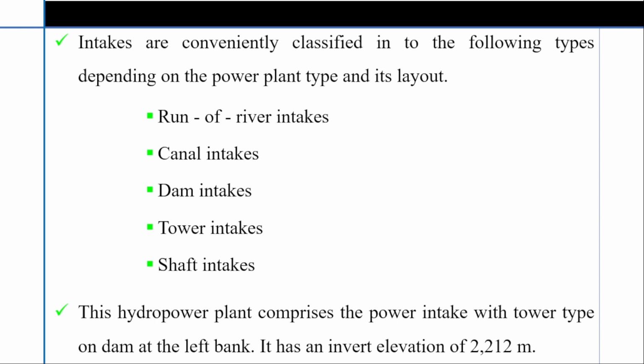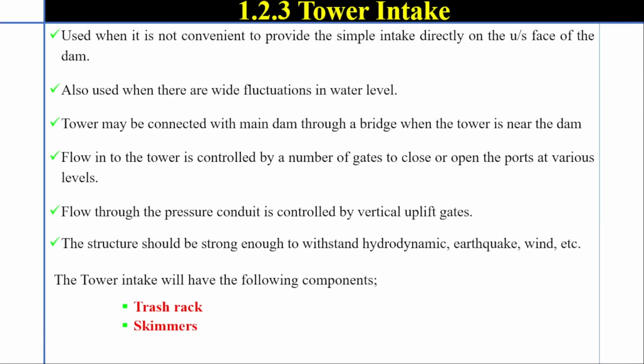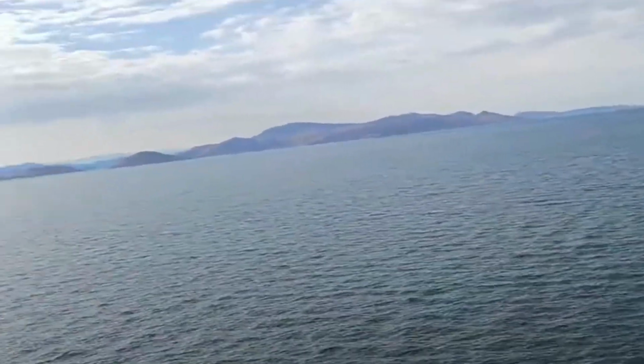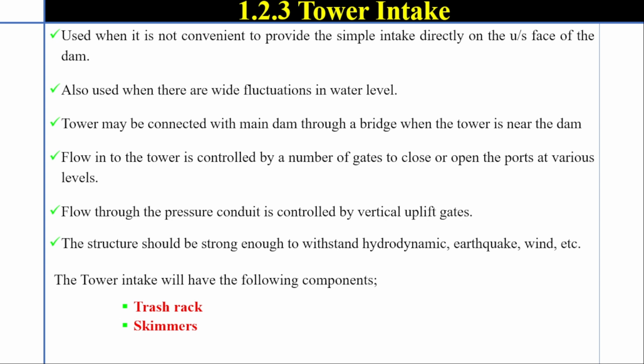This hydropower plant comprises the power intake with tower type on the dam at the left bank. It has an invert elevation of 2,212 meters. A tower intake is used when it is not convenient to provide the simple intake directly on the upstream face of the dam. It is also used when there is wide fluctuation in water level. The tower may be connected with the main dam through a bridge when the tower is near the dam.